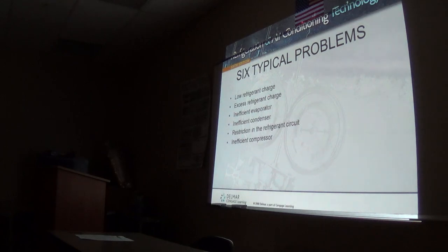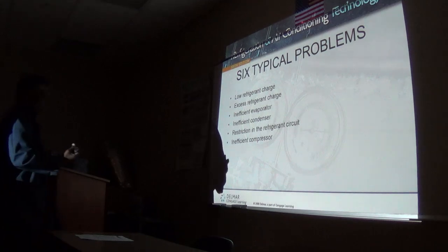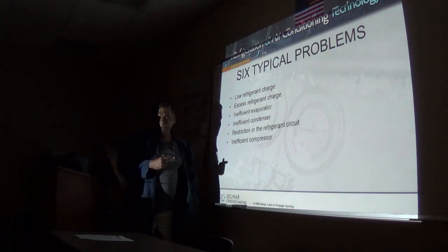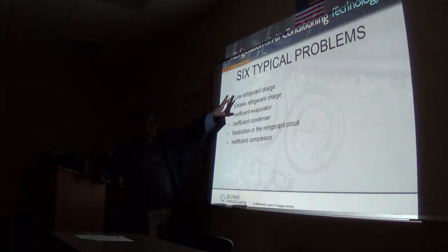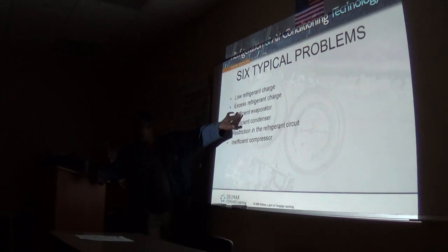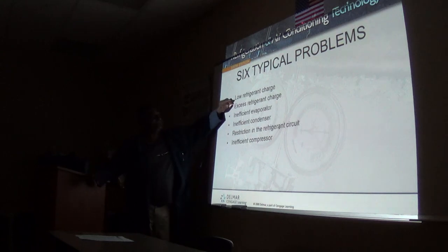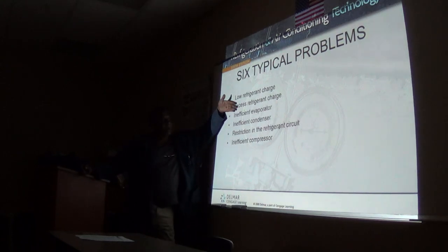Typical problems, this is troubleshooting, right? Low refrigerant charge, you need to know. It's amazing what superheat and subcooling right here will tell you about whether I have a low refrigerant charge or excess refrigerant charge. I mean, your gauges will show you, but you need to know the concept of how to calculate this superheat and subcooling.